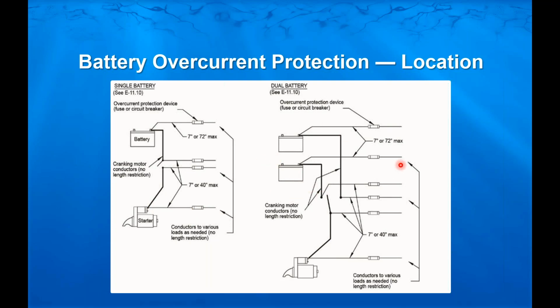Over in our slightly more complicated diagram, no difference there. Again, only the wires that are connected directly to a battery are allowed that 72-inch maximum distance on our overcurrent protection. Everything else has got to be within 40 inches. And what makes that exception possible is that we have to protect this section of the wire with some sort of loom, some sort of covering to physically protect that wire from being damaged, from the source of power to where it connects to the overcurrent protection device. In all these scenarios, that piece of wire between the connection and the overcurrent protection device has got to be in a piece of sheathing of some sort.